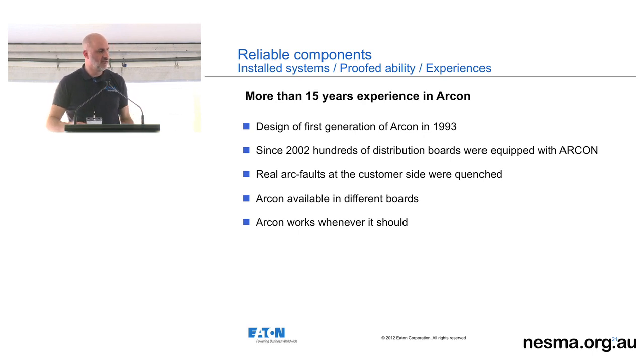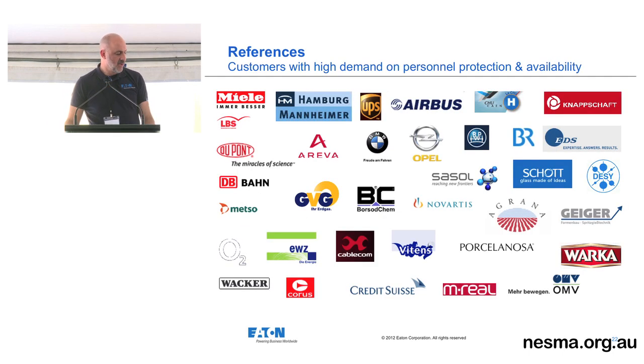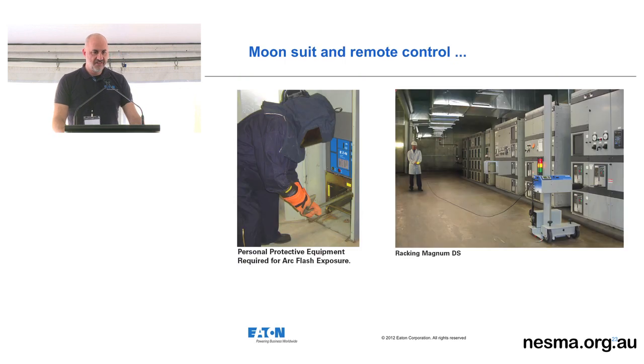Because of its self-diagnostics, it's always making sure that it's ready to act and there aren't any fault conditions within. Some of the major companies that have adopted the arc quenching system, as you can see on that slide there. Now, in the current situation, to offer the same sort of personnel protection, you either have to use the moon suit you see there, or some use a remote racking system. Quite expensive options there.